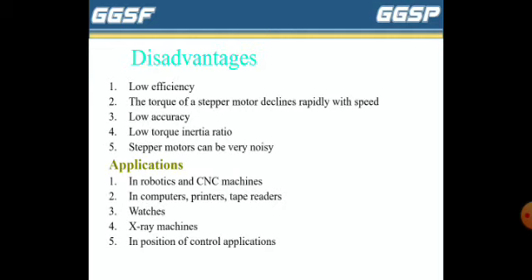The disadvantages of stepper motor are they have low efficiency. The torque of a stepper motor declines rapidly with speed. As the speed increases, the torque of the stepper motor decreases. The accuracy is low. The torque to inertia ratio is low. Stepper motors can be very noisy.